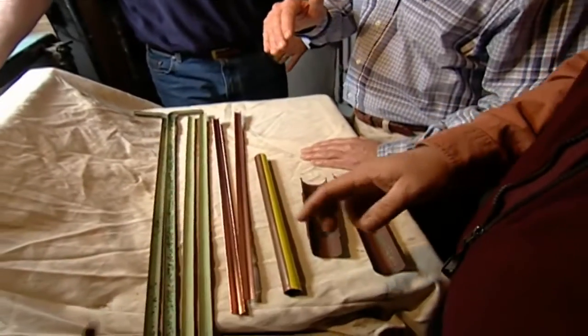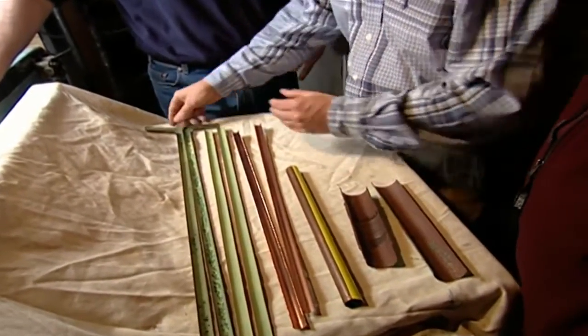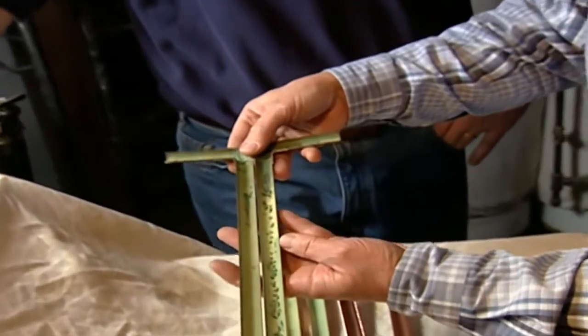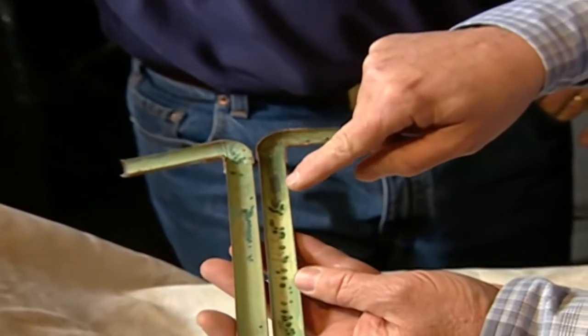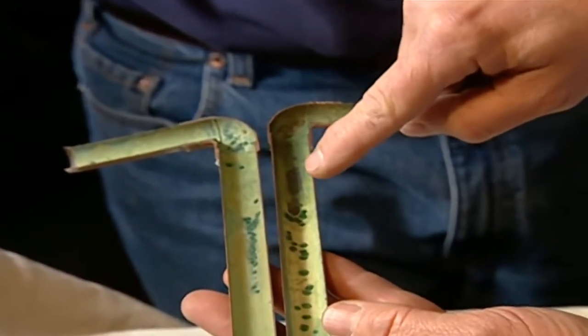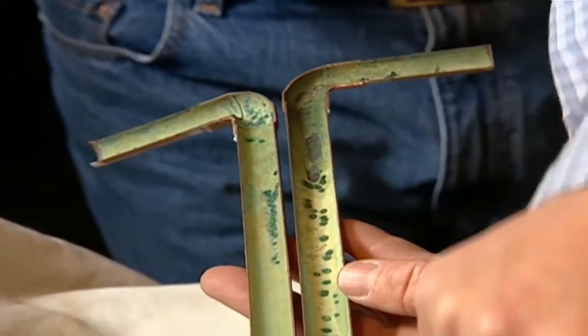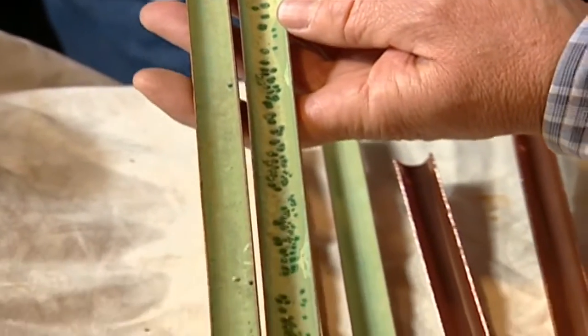When excessive flux is applied on the inside of the joint, it can remain after the pipe is put in service. This sample shows a residue of flux on the inside just downstream from this soldered joint. Once the flow started, it picked up this residue and it redeposited it. So each one of these is a pit point inside the pipe.